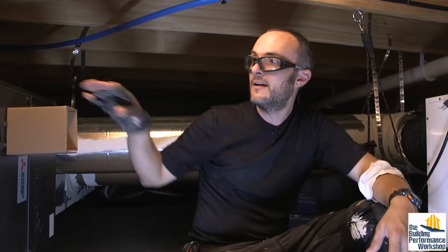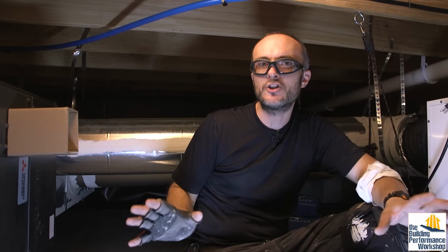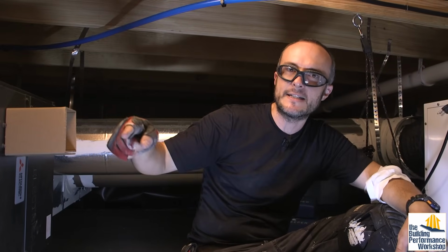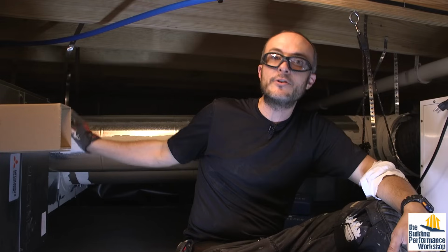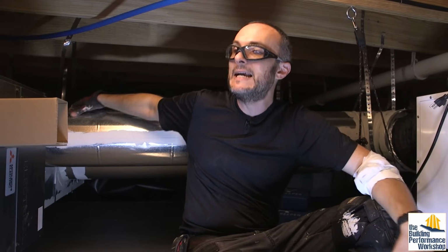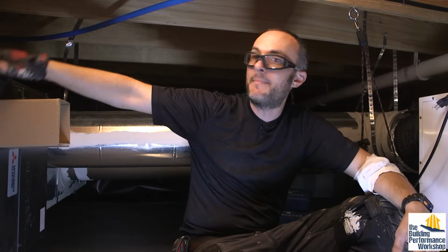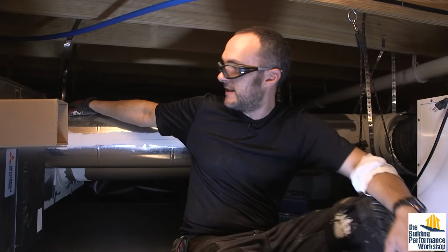So you're not going to have the condensate coming out of this, apparently, which is part of the way that it's designed to work, and so it just kind of shoots the efficiency of this entire system in the foot if you dump this into the return side. So everybody right now is trying to get people to dump the dehumidifier output into their supply plenum so that it bypasses the equipment entirely, and that's what we've done here.